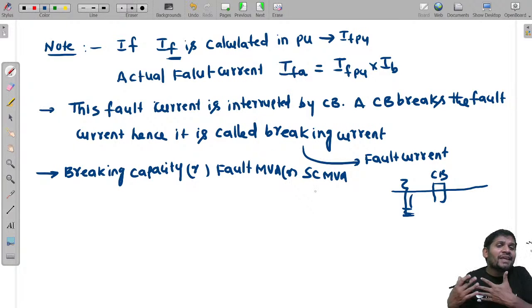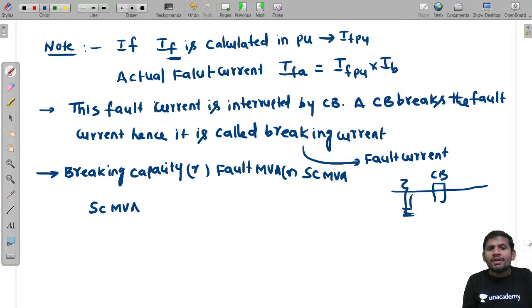But what is this breaking capacity? In terms of MVA, we want to tell. That is fault MVA or short circuit MVA. Then what is the short circuit MVA, sir? Very important formula to solve the problem, sir. The short circuit MVA equals root 3 into, because it's a 3 phase, base voltage into base current, sir.